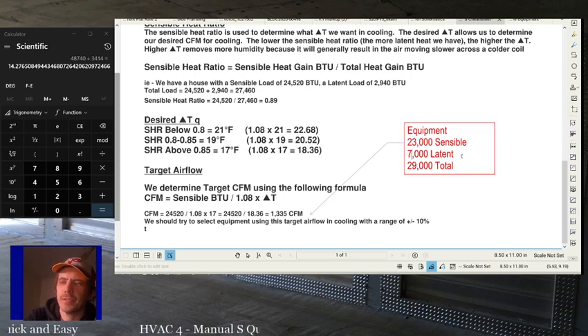As a matter of fact, let's change this real quick. Let's make this 7,000 so I know this math will work, because I'm starting to think this math's not going to work out. Alright, so we found a piece of equipment. It's 23,000 sensible, 7,000 latent, 30,000 total. Alright? Our sensible is not enough to meet the 24,000 BTUs we have sensible.